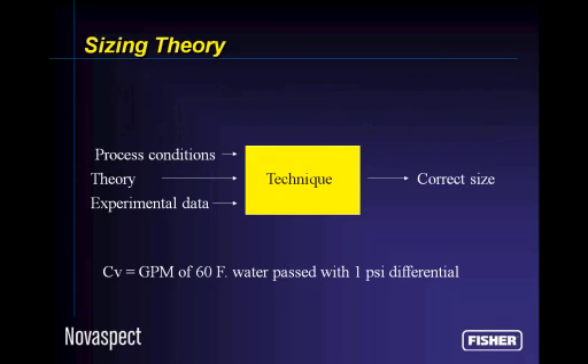We take your process conditions, a little bit of fluid dynamics theory, which essentially is derived from some physics. We take some experimental data regarding the valve type itself, the specific valve, and we do this in the factory. We run our valves through some very exhausting flow tests in our flow laboratory to determine various critical constants regarding it. We put that all into an algebra hopper, and we end up predicting the right size. And the size of the control valve is measured by the CV value that it needs to pass.